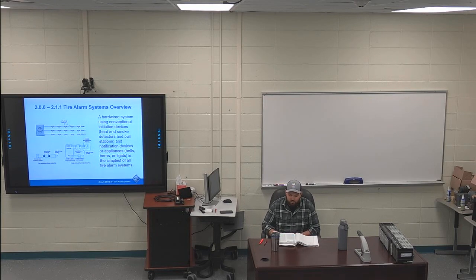You're going to need to know things like addressable device. Most of these fire alarm systems have an addressable device. For this room, for example, we have a smoke detector right there. It's got a marker label on it, and it is addressed to this classroom, B144. So if we have a smoke or a fire in this classroom, the fire panel knows that this classroom has an alarm because it's addressable.